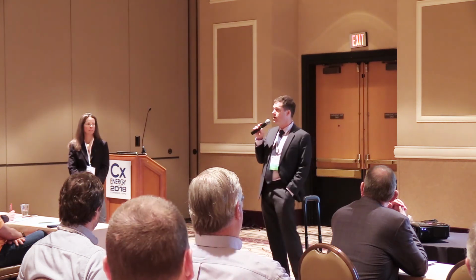Can you speak to the integration piece at all, how you take data from your EMS into SkySpark? That's the most challenging piece. I'm not a technical expert on it, and we often run into issues. Open protocols are key, and getting through the firewall is the key factor. I'm trying to be non-proprietary as much as possible, but the systems we have the biggest problems with are Siemens, to be honest. Siemens Apogee locks it down pretty hard, and it's hard to tie into. Anything BACnet IP, we're good to go. BACnet is pretty easy, we can tie in.